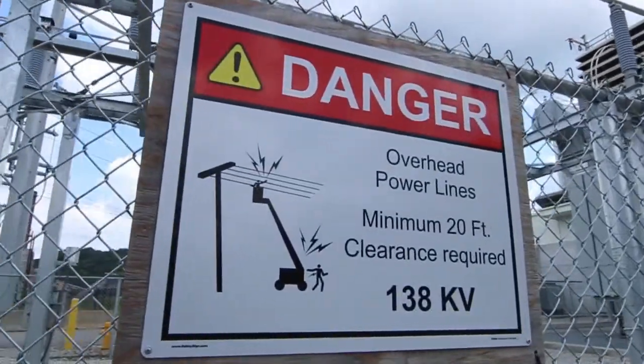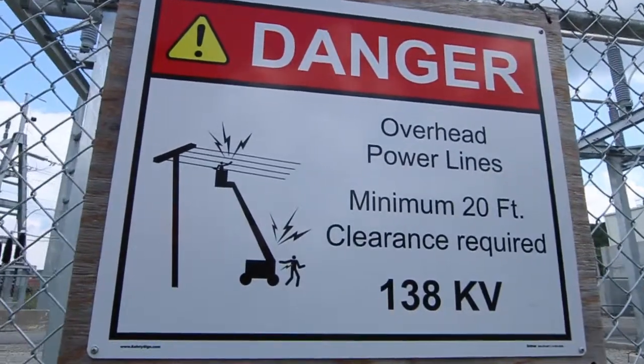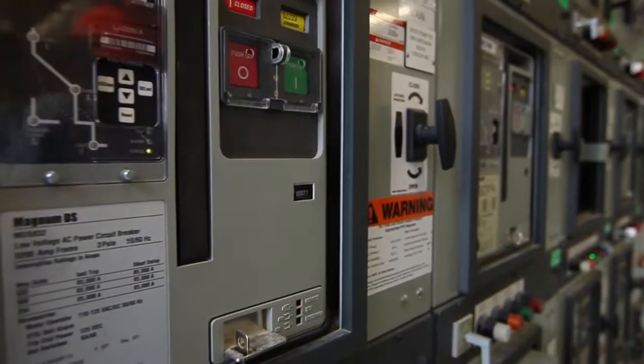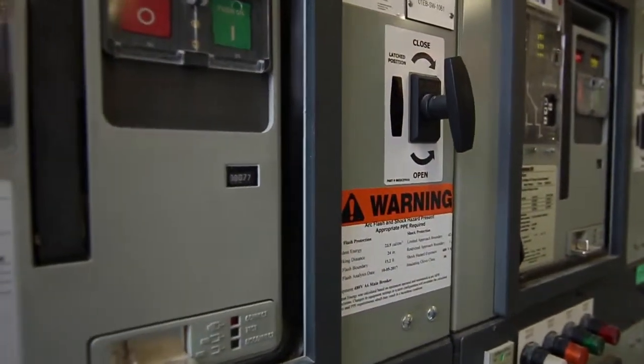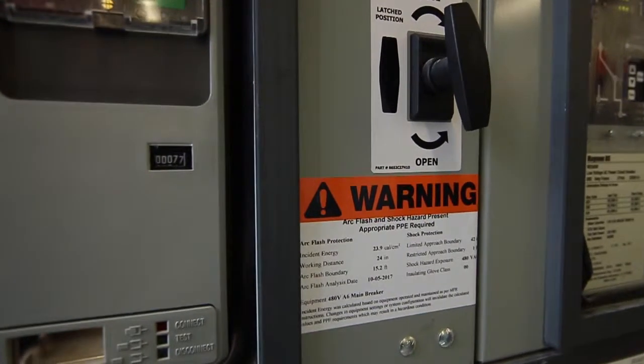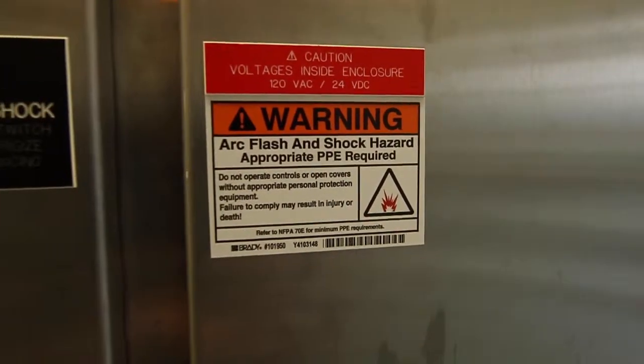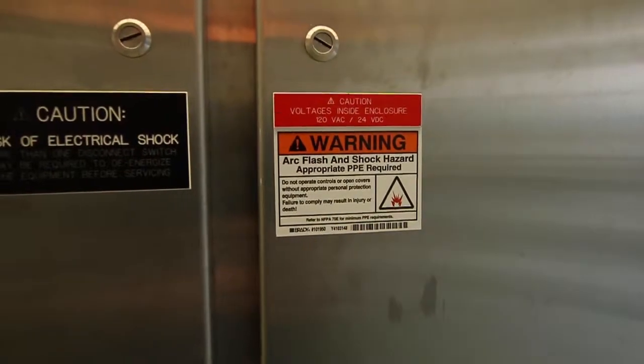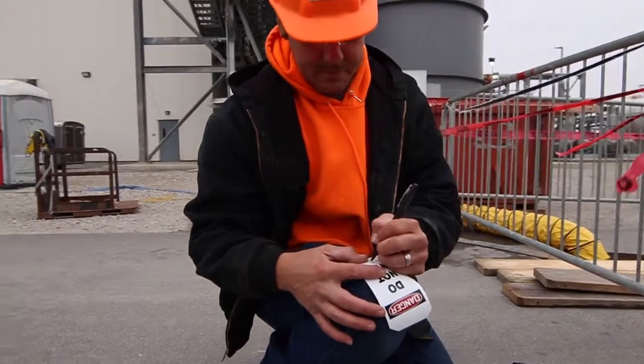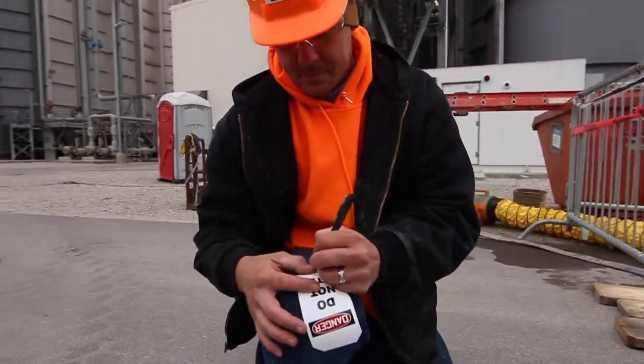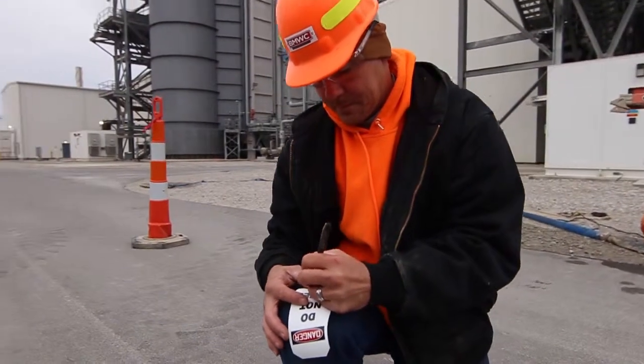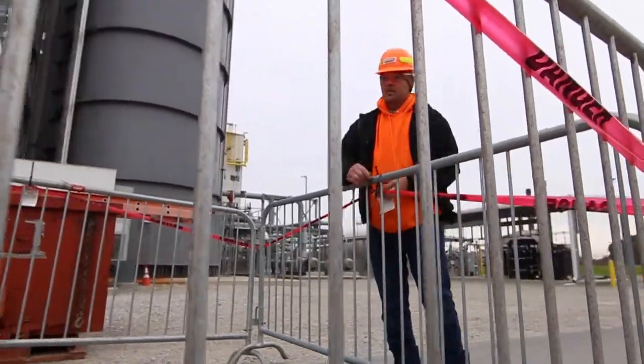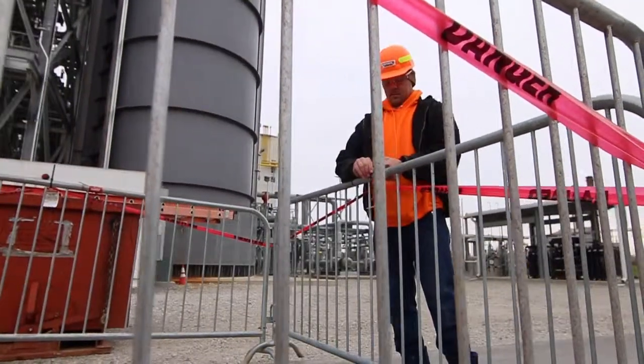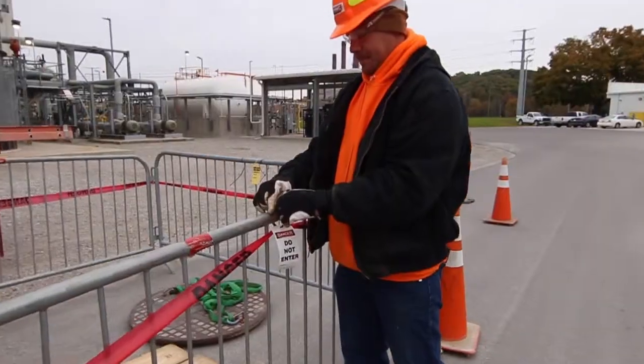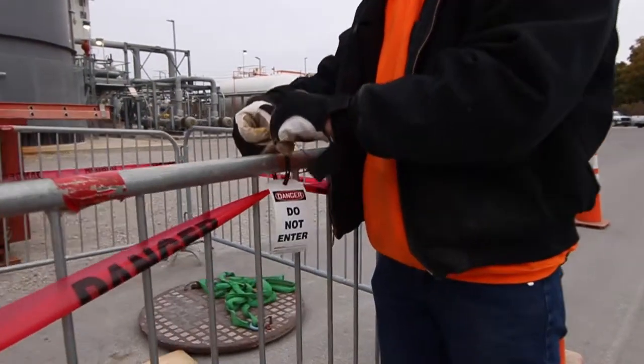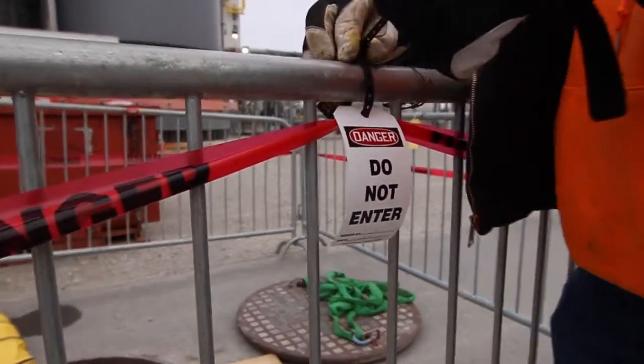Examples where FR clothing may be required include, but are not limited to, validating electrical energy isolating devices. Contractors must ensure that their employees are provided with and properly use personal protective equipment to ensure protection from shock and arc flash hazards. Barricades must be used in conjunction with warning signs to prevent or limit access to work areas containing live parts. Barricades must be placed no closer than the flash protection boundary, which is at least 4 feet from live parts unless the equipment is labeled otherwise. However, contractors must comply with the posted calculated distance for the flash protection boundary.